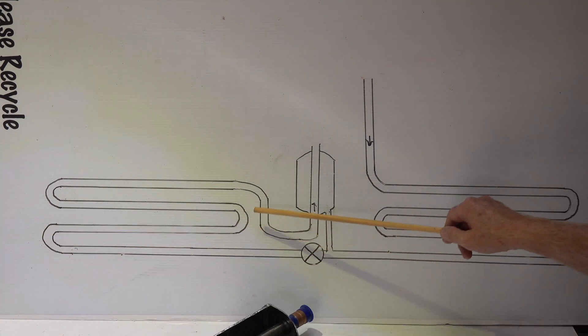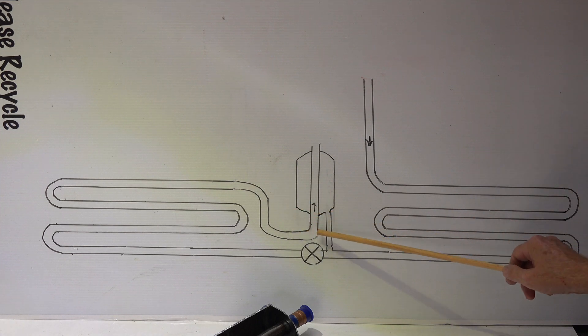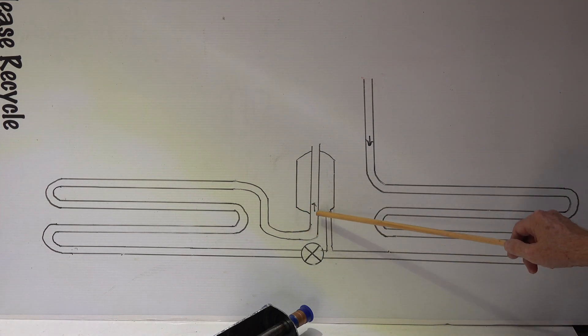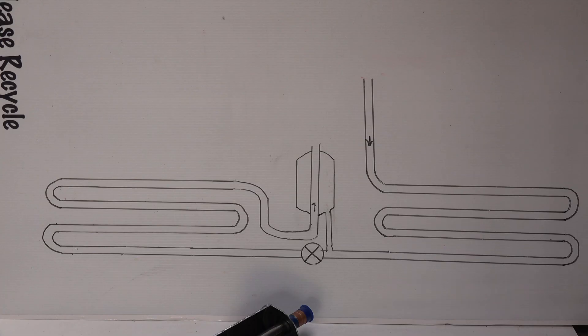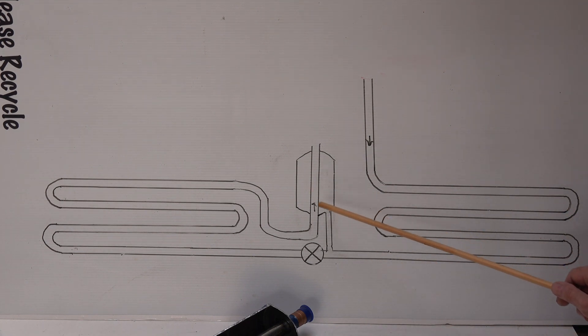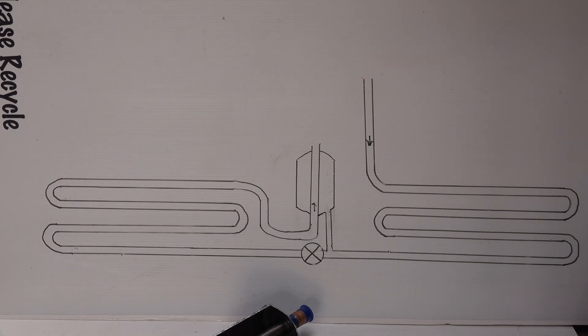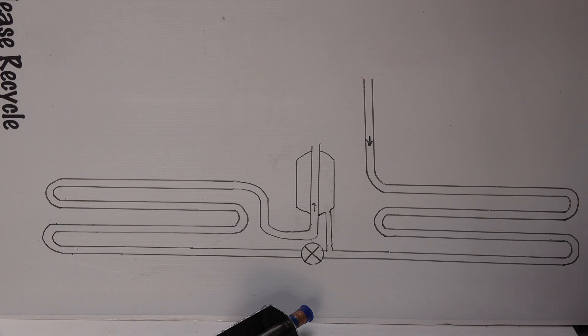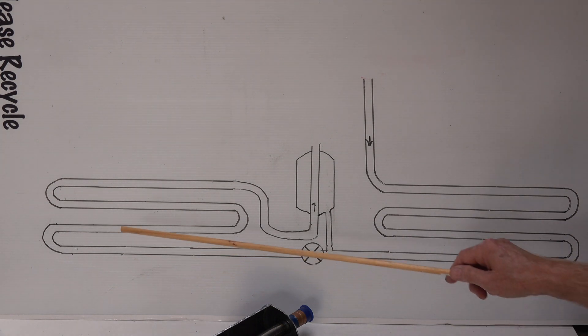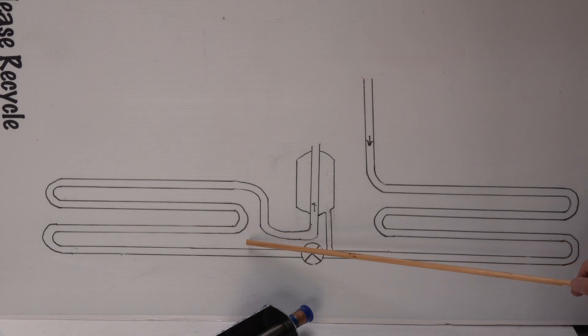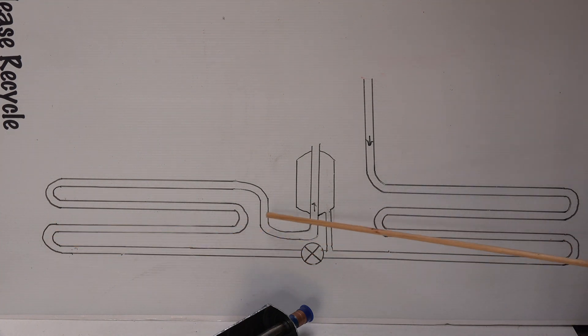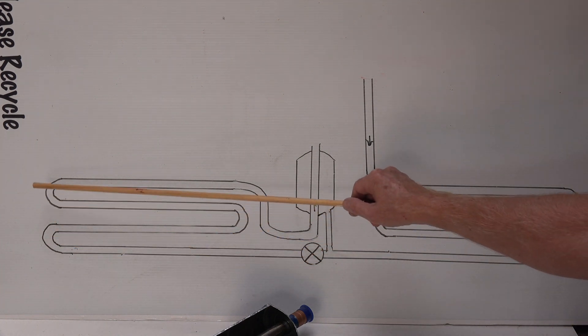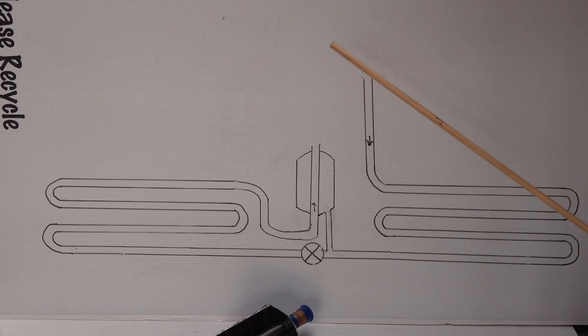To the suction line which goes through this compensator. Now what's going to happen with this system is when it's colder outside there's not as much refrigerant necessary. So what we've got is it's not evaporating as much refrigerant here in the evaporator as it would normally.